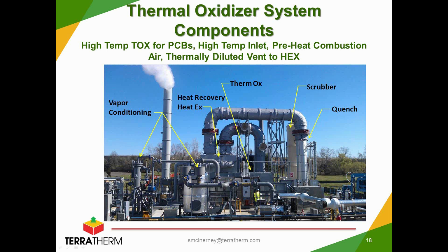This site, if you're following the cursor, we used a heated inlet line, so the strategy was not to cool and condense for the higher temperature phase of this project, but we wanted the highest temperature we could maintain going into the oxidizer, so that we didn't need to make up more supplemental fuel to get up to the operating temperature of this unit, which was approximately 2,300 degrees Fahrenheit with a 2-second residence time.